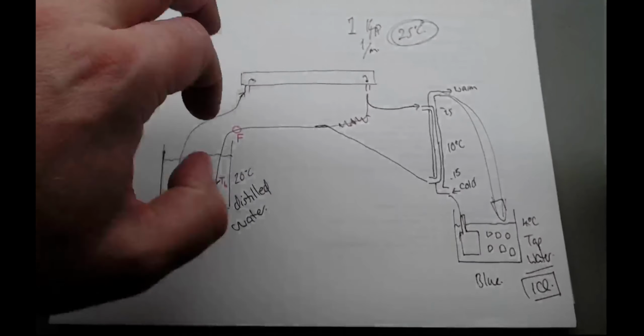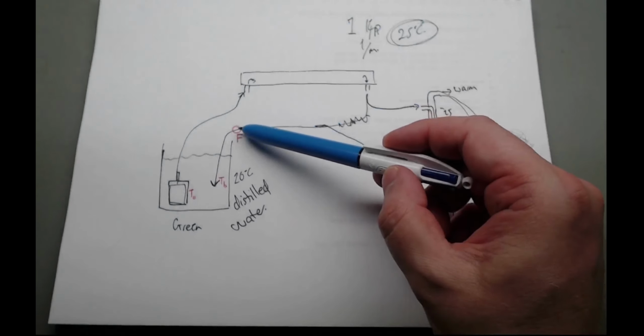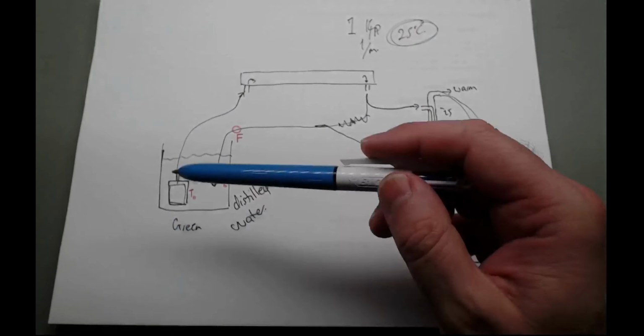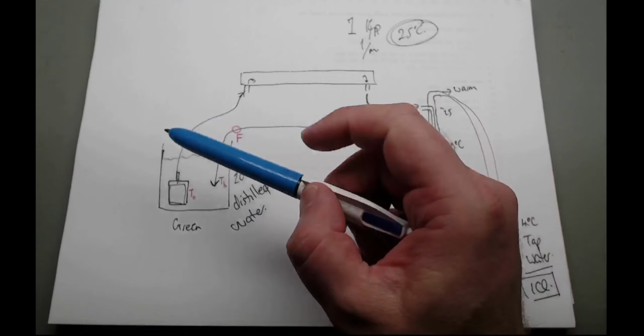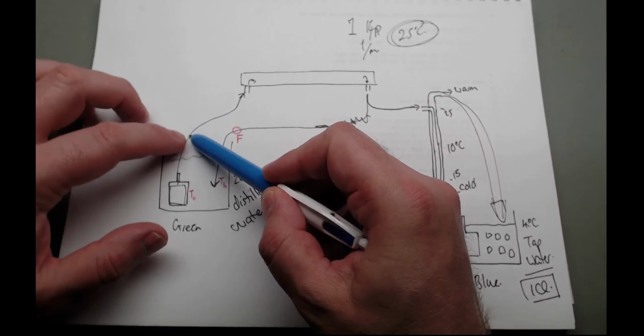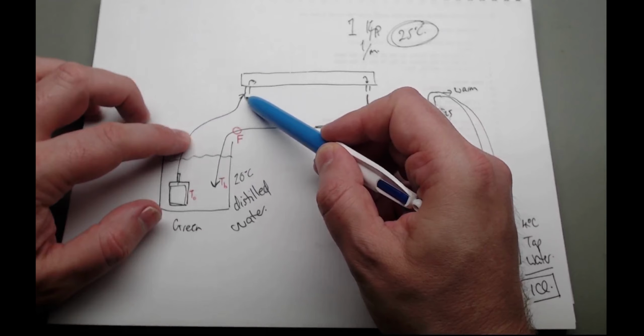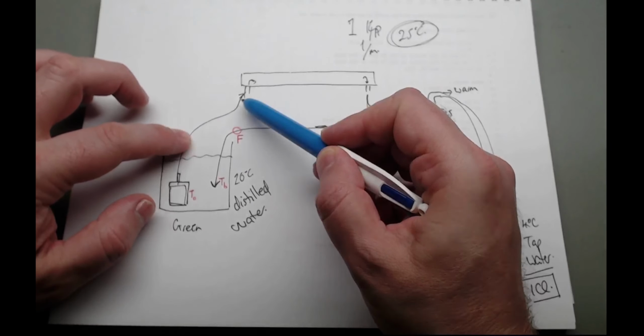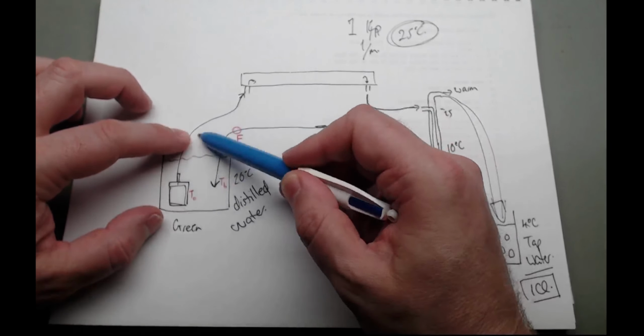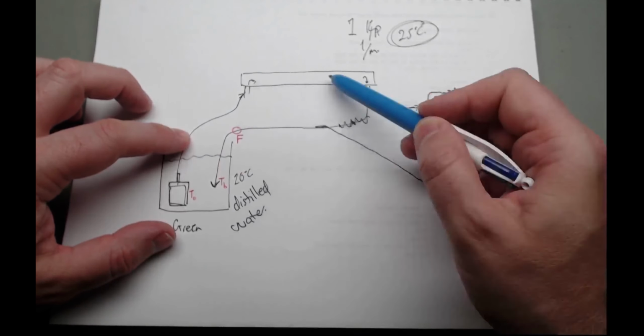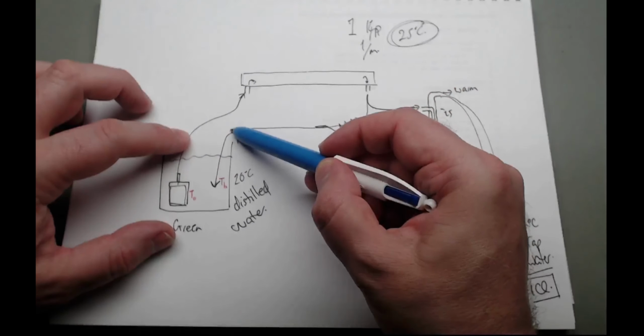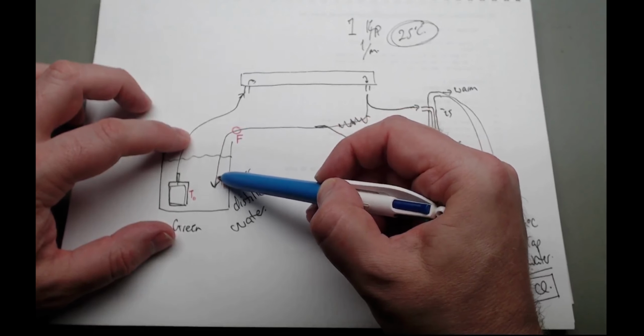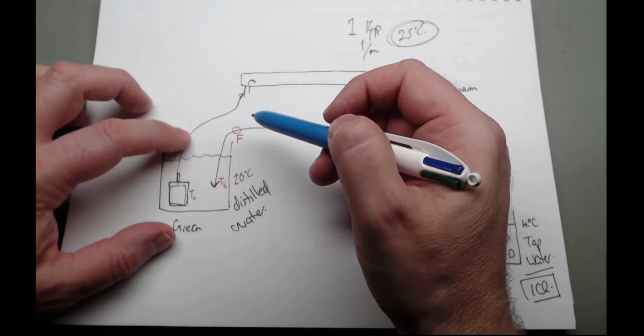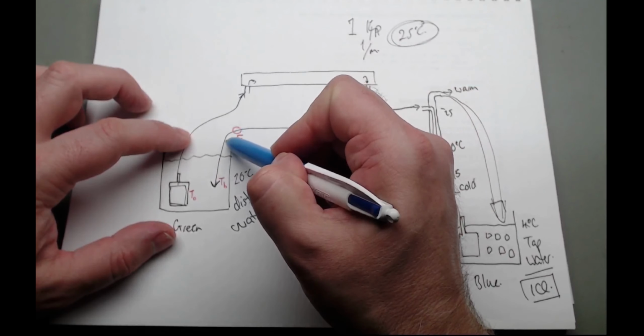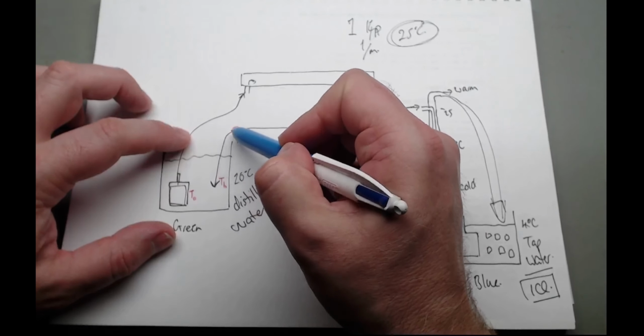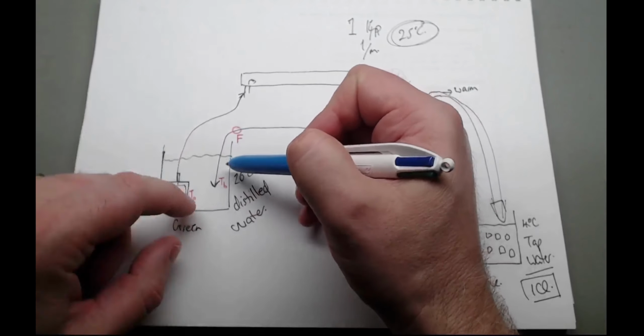Now, one question a friend asked me was, why have I put the flow sensor here, not here? Because realistically, if I put a flow sensor here and the pipe pops off here, it'll still measure tons of water flowing out, but there'll be no cooling. So I've put the flow sensor as close to this end of the pump. And if you look at the pictures, the flow sensor's pipe actually terminates - out of the flow sensor is the dump into the tank.